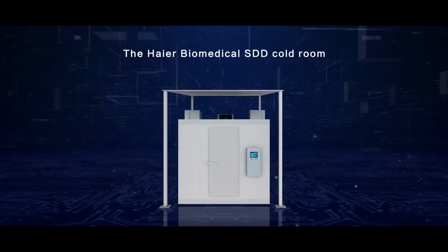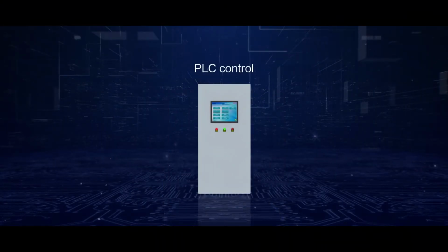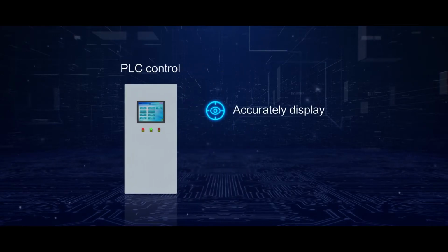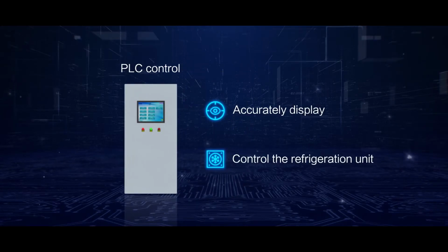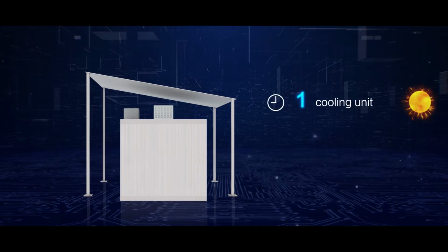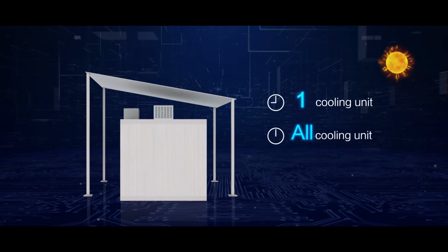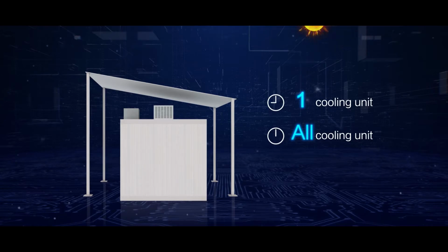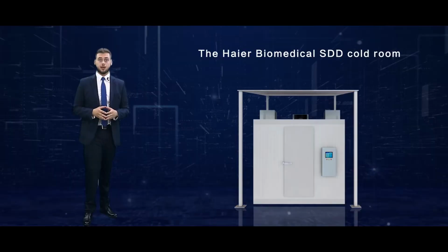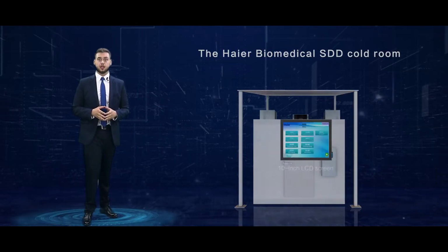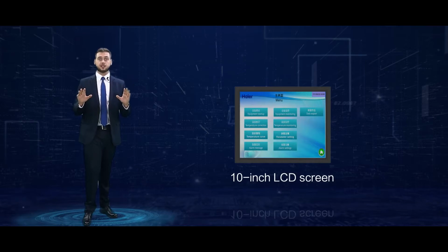The Haier Biomedical Solar Cold Room adopts PLC technology. It can accurately display and control the refrigeration unit to make the temperature more uniform. Meanwhile, the PLC can start the cooling unit based on the solar radiation to fully use the solar energy. For example, starting only one cooling unit around 9 a.m., and then the other 3 to 4 units will start during midday, according to the requirement of the cold energy compensation. The Haier Biomedical Solar Cold Room comes with a user-friendly 10-inch LCD screen.